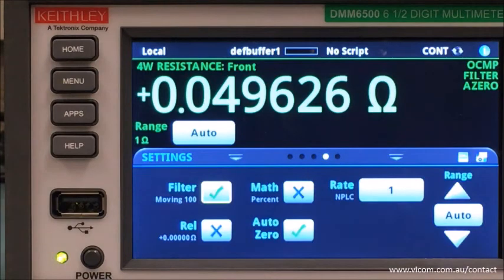Let's return to the home screen. Now you see we have a very smooth output of what we are trying to measure, which is our device under test of 50 milliohms. Notice that we are within the 1% tolerance, so just above the 49.5 milliohms of the lower limit.